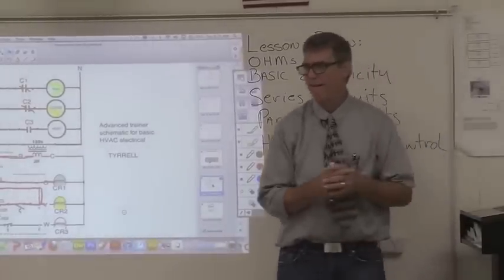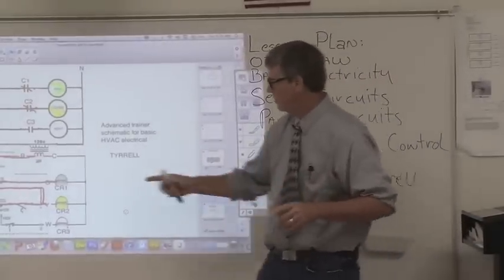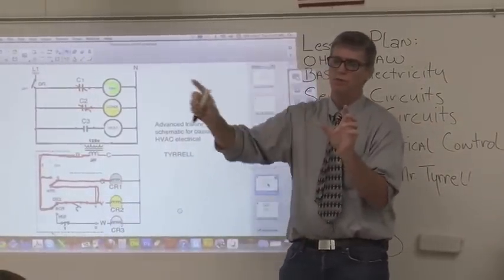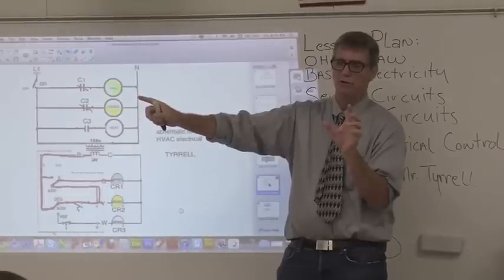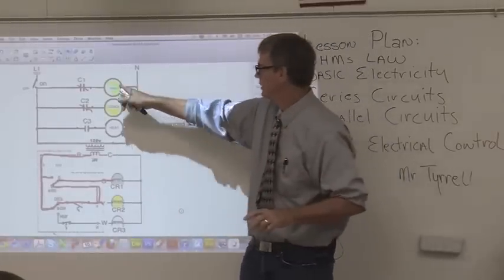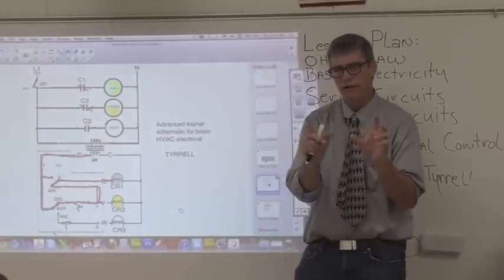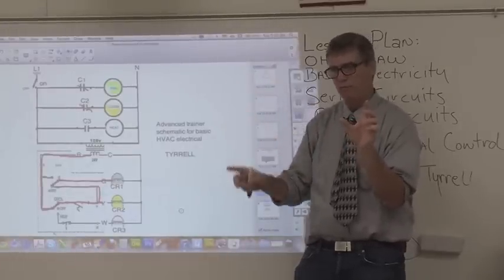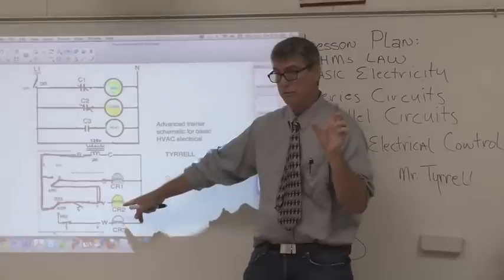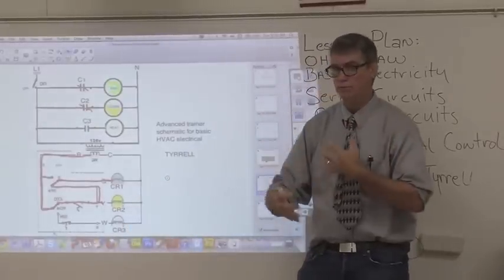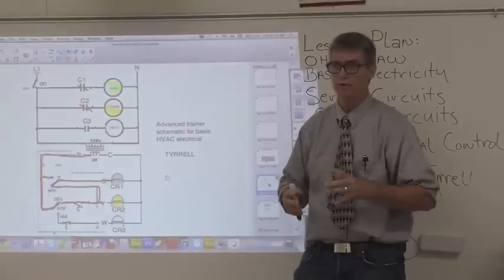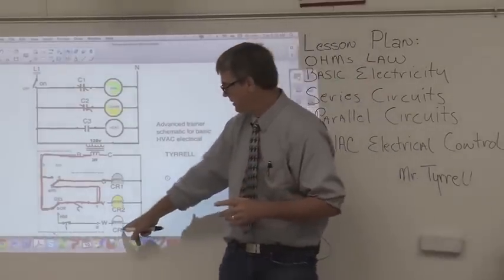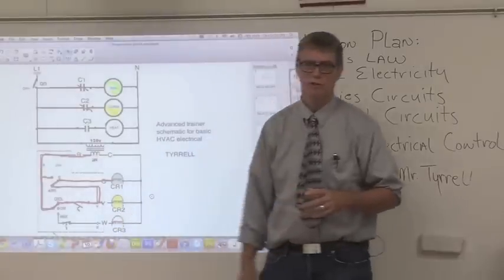G is the terminal inside the thermostat that sends 24 volts out to start the indoor fan motor. Y is the output of the thermostat that starts the condenser and the compressor. The compressor is the heartbeat of the whole operation — it starts the whole cooling cycle. And W is what starts heat.